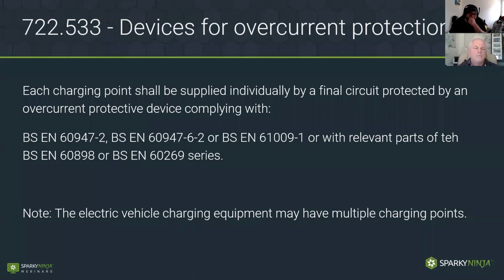Overcurrent protection, we just need to make sure we have suitable overcurrent protection to BS EN 60947-2, BS EN 60947-6-2, or BS EN 61009-1, which is an RCBO. Or we could use relevant parts of 60898 or BS EN 60269, relevant parts being just overcurrent protection. Okay, it's worth noting that it does say that electric vehicle charging equipment may have multiple charging points. So it might be that you have multiple charging points from one, so you may have to have, in that case, individual overcurrent protection, like with all scenarios, like even with caravan parks, the overcurrent protection would be individual. Protection is always individual in that scenario.